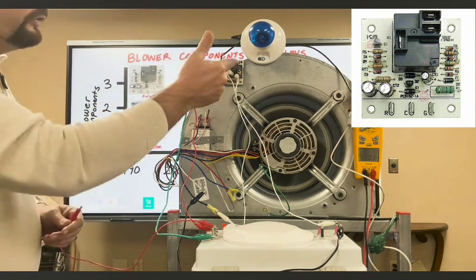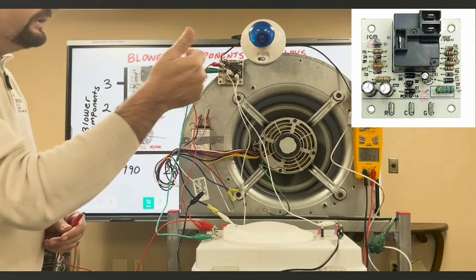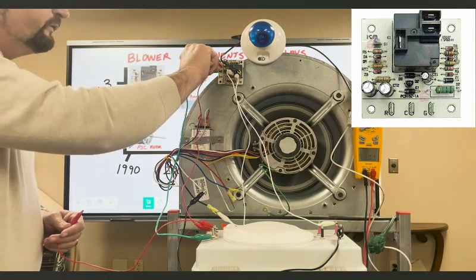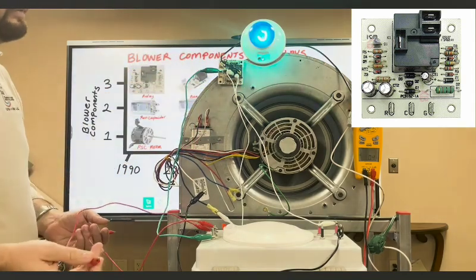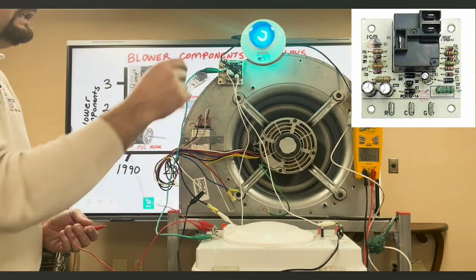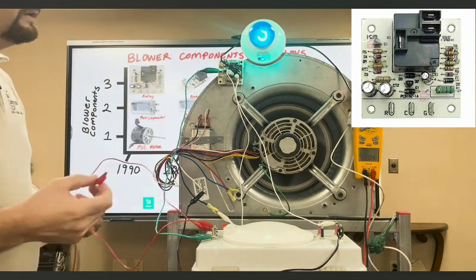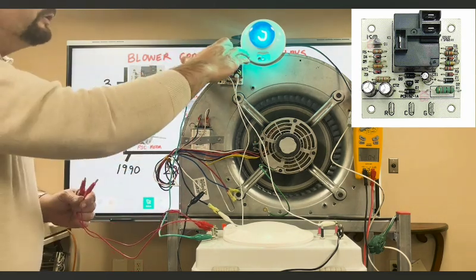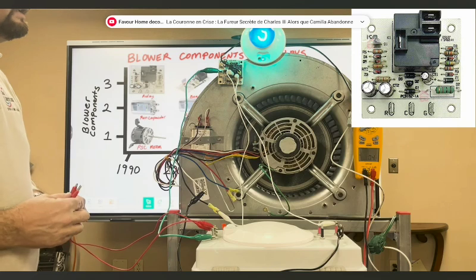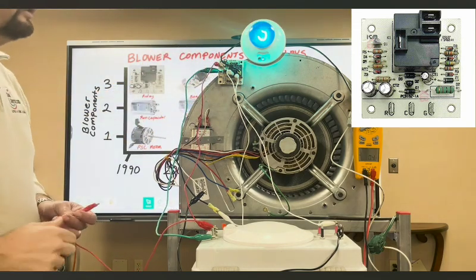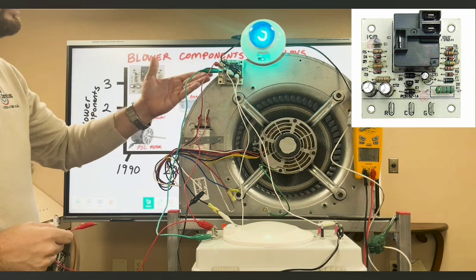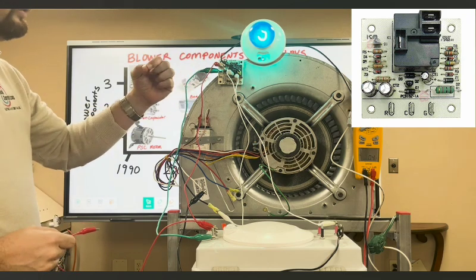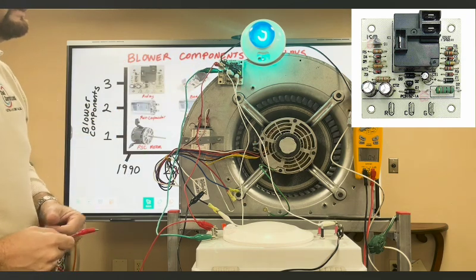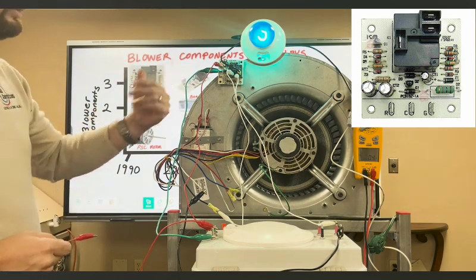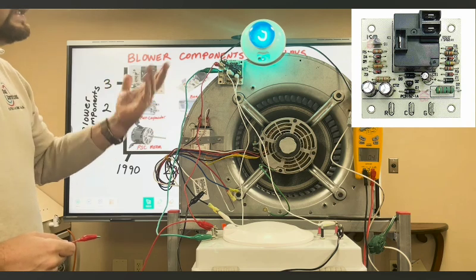Another way too, if you think your timer is stuck, you can always remove 24 volts here. It should shut off immediately. If it's still running and you have no 24 volts there, then you have a relay that is stuck in the closed position. So that's another way of quickly troubleshooting this. And on pretty much any blower control board, you can remove the 24 volts on the board if you think the relay is sticking. And if you remove 24 volts on it, they should immediately shut off.